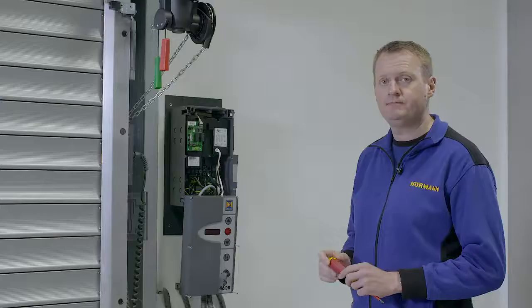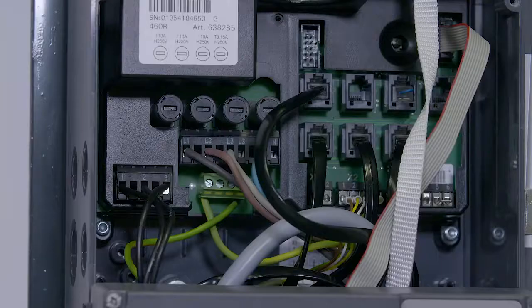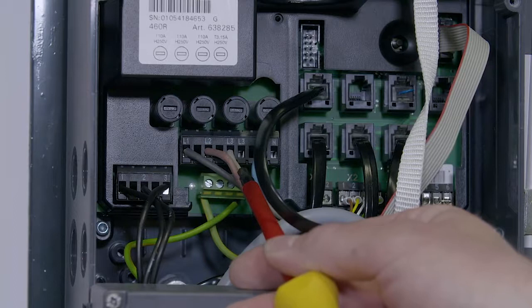If the door closes, isolate the door and change incoming phases L1 and L2, not the supply coming from the control panel to the motor.